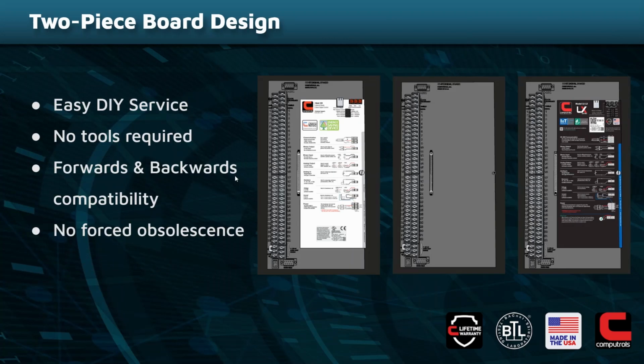So we talked about forced obsolescence and product churn, right? Things becoming obsolete, how do you address that? One of the cornerstones that Roy and Kevin envisioned was designing products that sit on the same platform. Notice the terminations are made on a backplane, and the electronics are in the form of a card that snaps in and out. This gives you two primary benefits. The first is serviceability: you don't need any tools or special programming to swap out a controller and troubleshoot it. Drop in the new one, change its address, and the software automatically downloads to it.